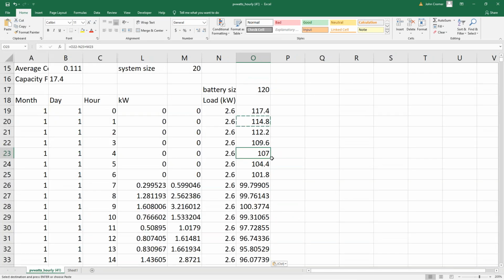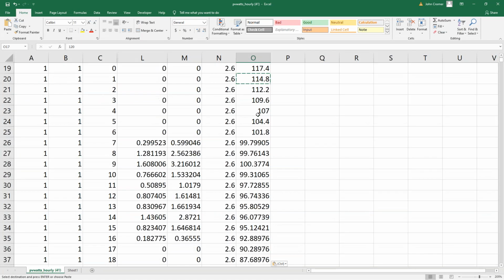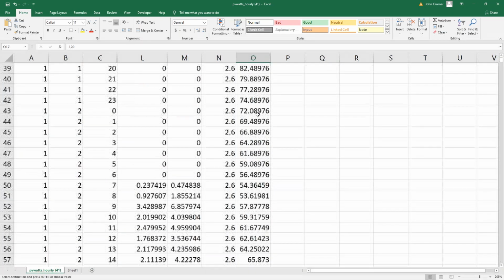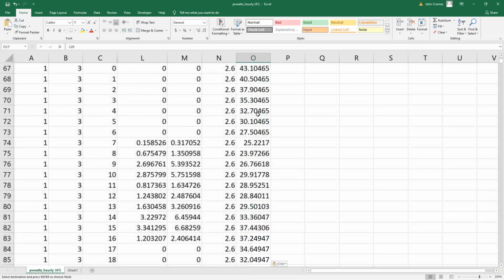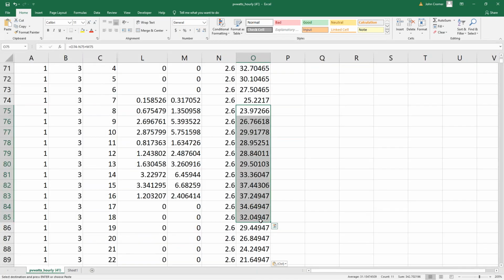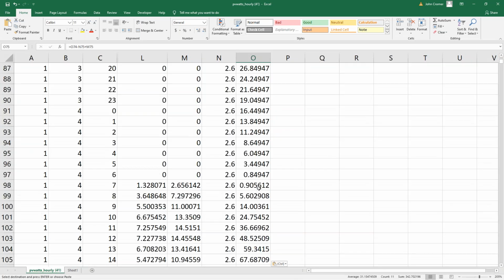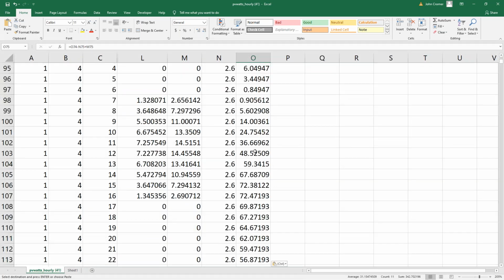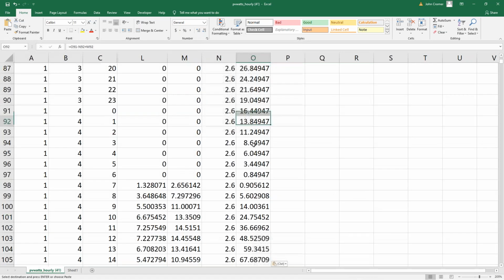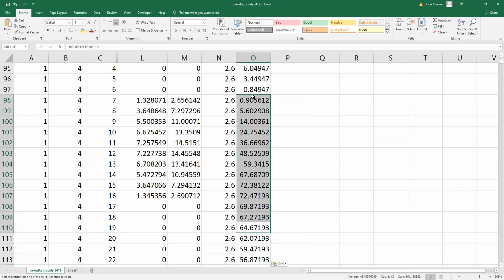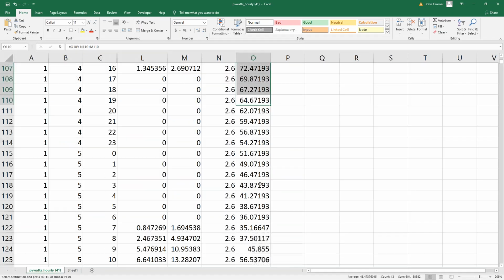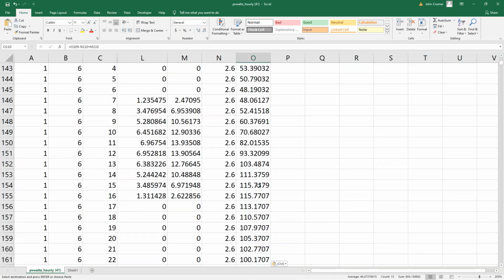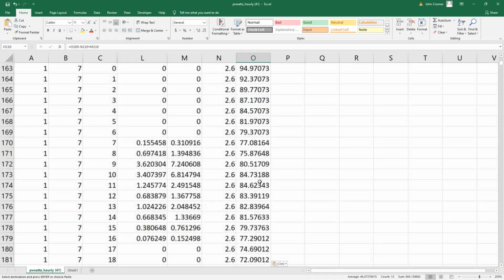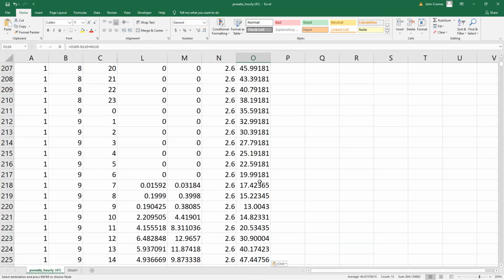So what we can see in our battery bank is we're assuming a starting size of 120 kilowatt hours, and we're drawing out of it. In the wintertime, it keeps going down and down. Now we're on like our third day and we're not producing as much power as we need, getting down into almost the very bottom of our battery. Then the sun comes back up and we surge back up to 70 kilowatt hours and we start draining again. Remember, our maximum in this case is 120 kilowatt hours, and we're going fine.